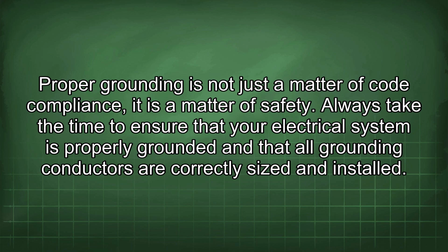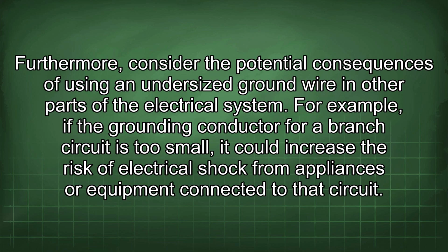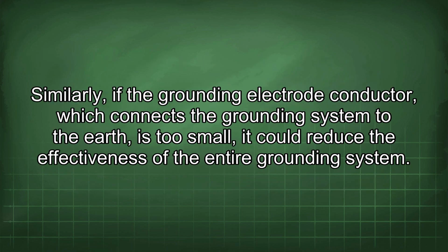Furthermore, consider the potential consequences of using an undersized ground wire in other parts of the electrical system. For example, if the grounding conductor for a branch circuit is too small, it could increase the risk of electrical shock from appliances or equipment connected to that circuit. Similarly, if the grounding electrode conductor, which connects the grounding system to the earth, is too small, it could reduce the effectiveness of the entire grounding system.